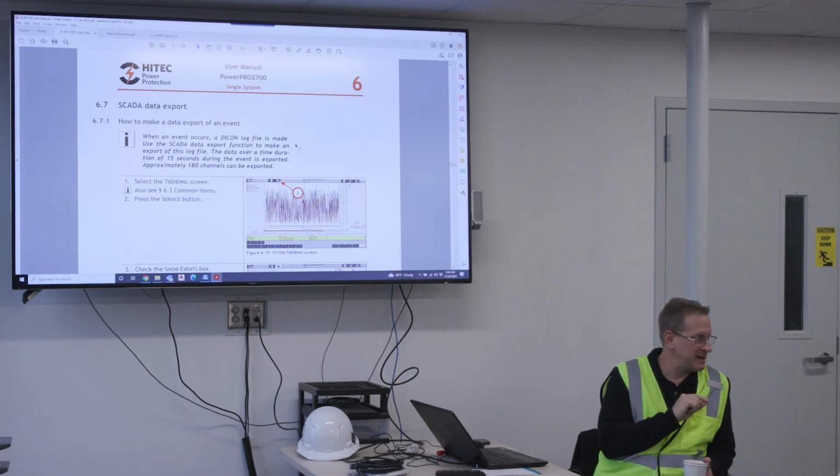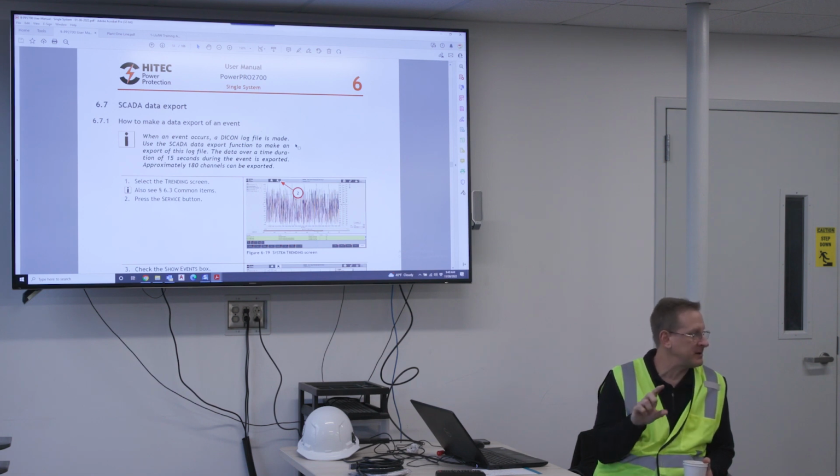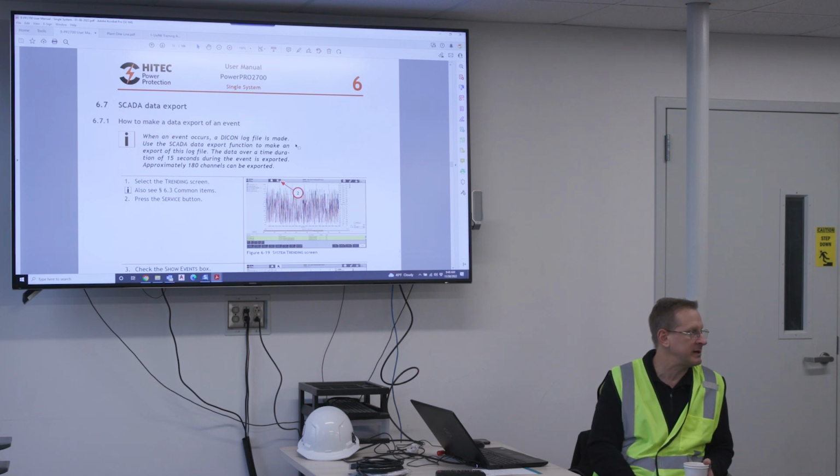The DICON has its own events that it will record separately from the SDP, but those are, let's say, more important events, the actual red alarms or the utility failures that the DICON will also take a snapshot reading for. And those are not available for your extraction. We have to send service people to extract those logs. But you would be able to extract, if you had SCADA running, you'd be able to see history of those as well as any superficial lower level alarm as well.